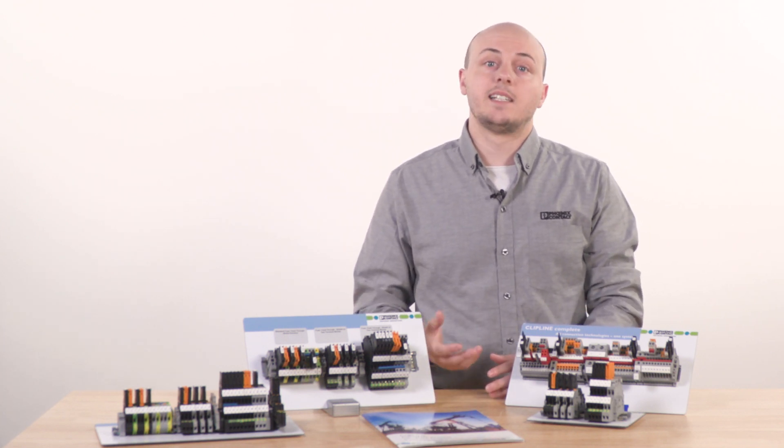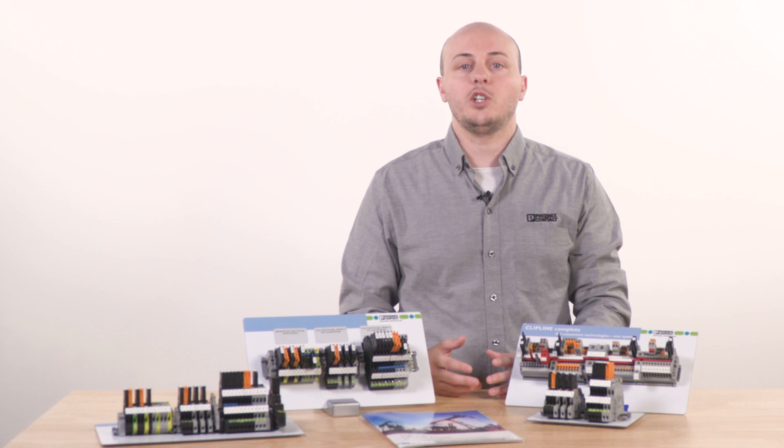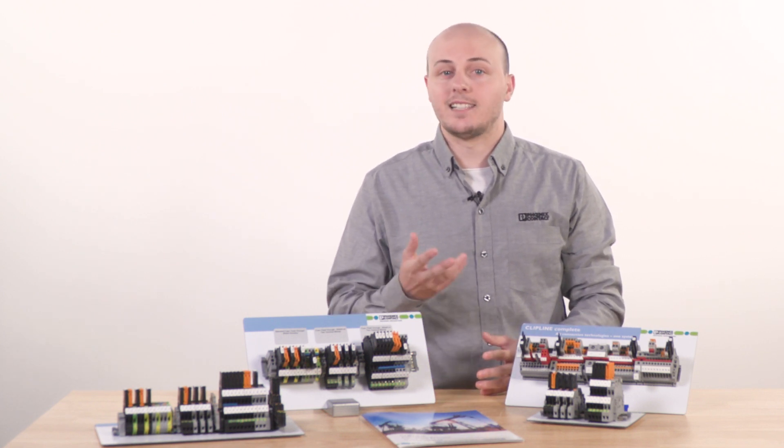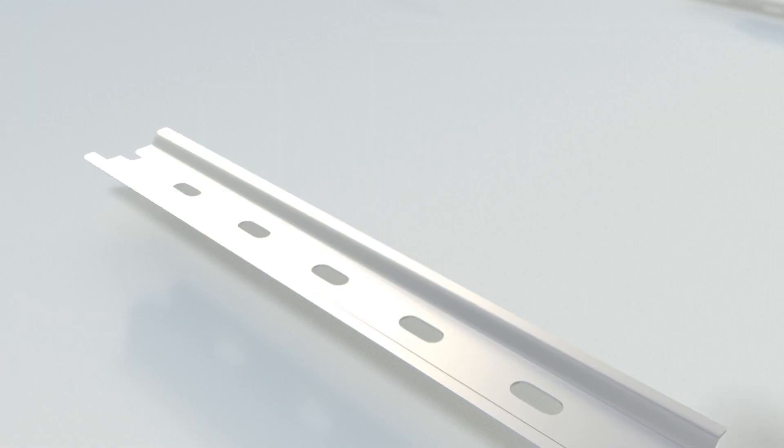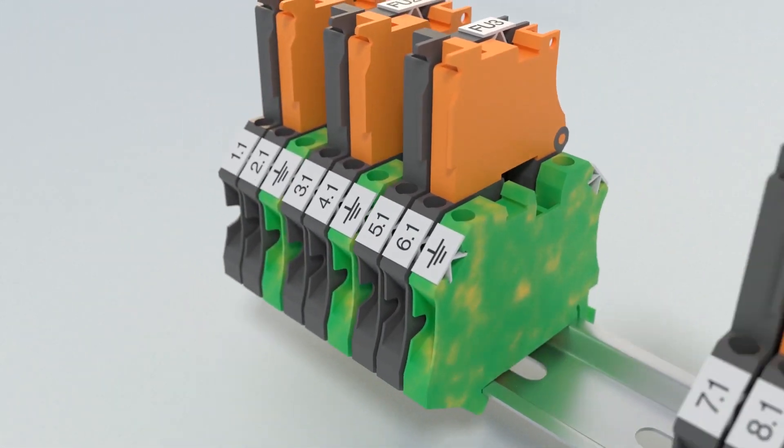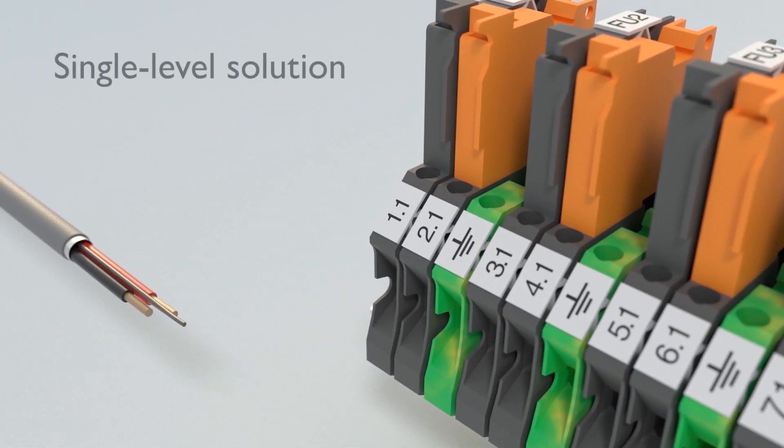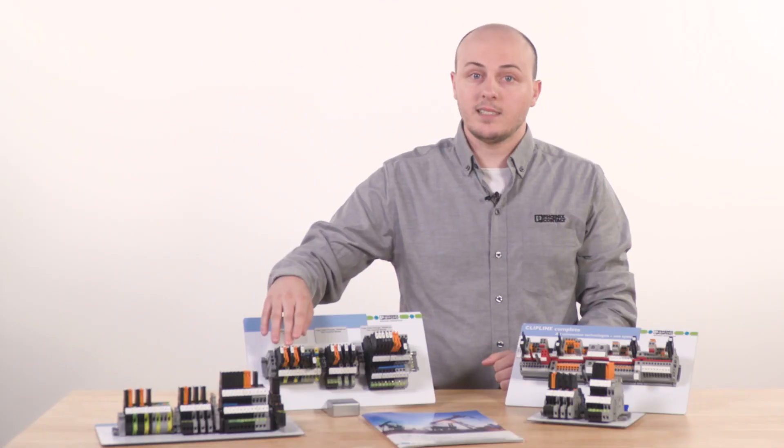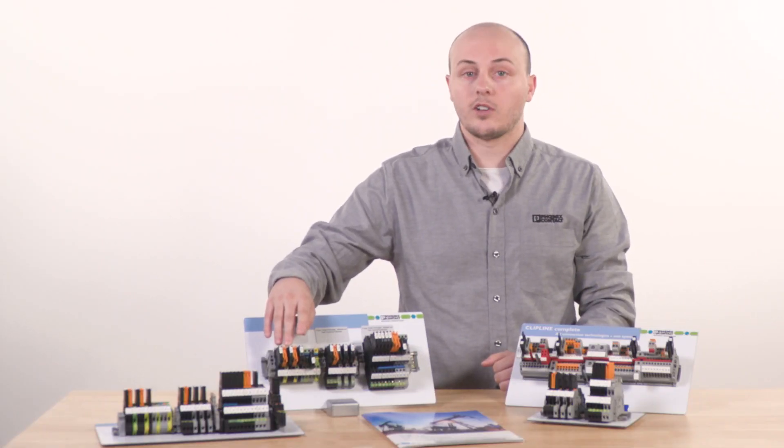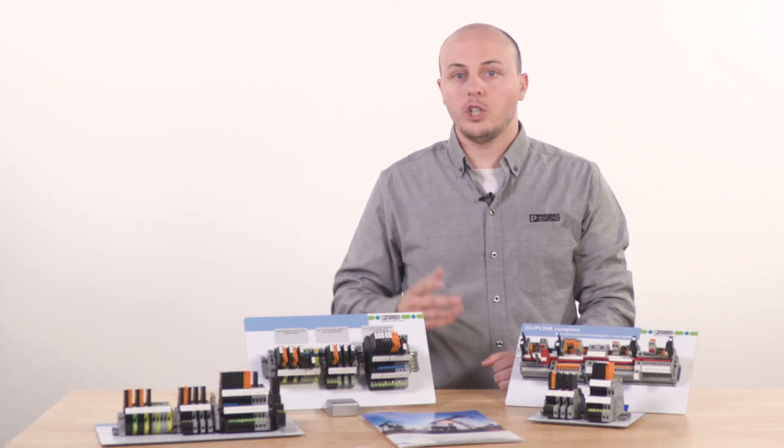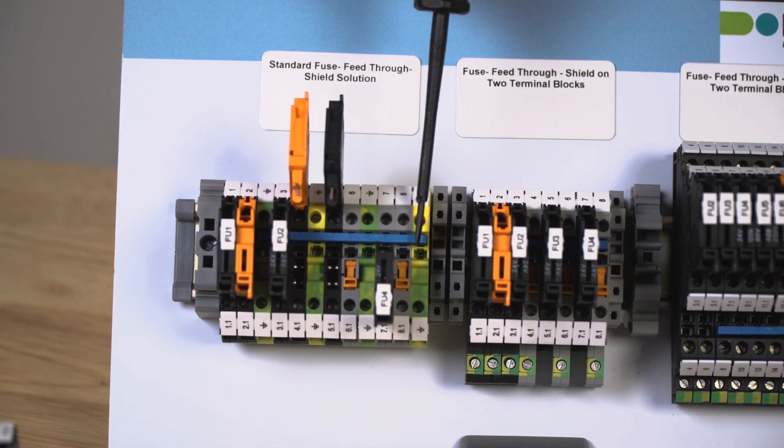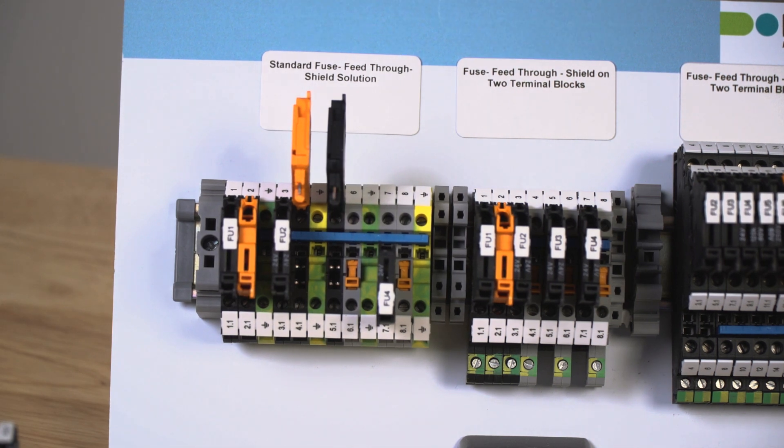Phoenix Contact has developed several terminal block configurations to aid in wiring and save space within the cabinet. The basic approach uses three single level terminal blocks: a fuse block for protection, a disconnect block to isolate the return, and a ground block for the shield connections. A unique plug-in bridging system allows for bridging to be easily added for quick and reliable potential distribution.